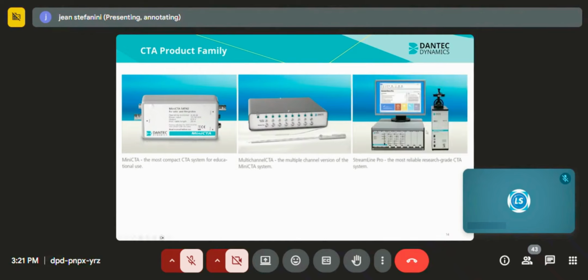So we have different systems. The low-end system has a frequency response up to 10 kilohertz, so you can measure fluctuations up to 10 kilohertz. That is the mini CTA, which is a single channel system. And this one is the same type of unit, but you can have multiple channels, up to 8 channels in one box, but still limited to 10 kilohertz. So why do we need more channels? The answer is because you may want to measure at different locations at the same time, or you may want to measure not only one component, but 2 or 3 components. And 3 components means 3 wires, and 3 wires mean 3 channels. So 1 wire is associated with 1 channel.